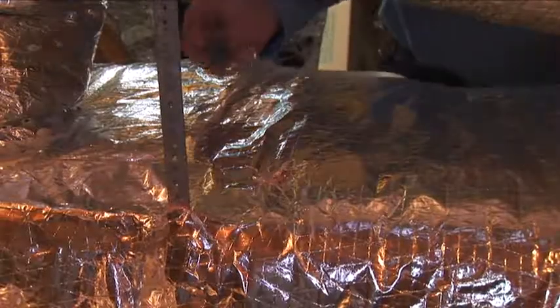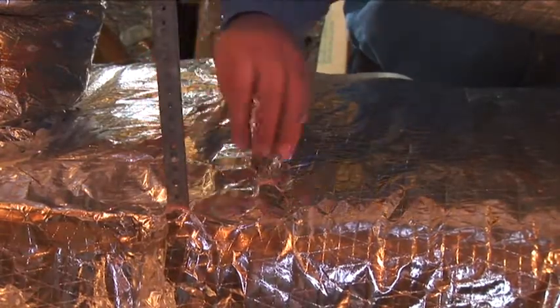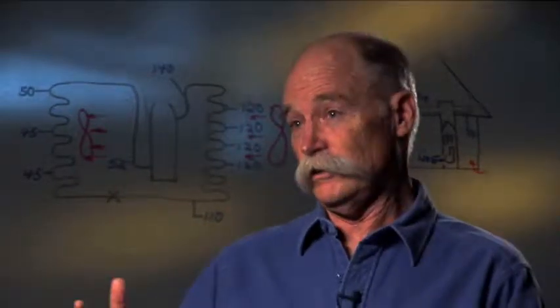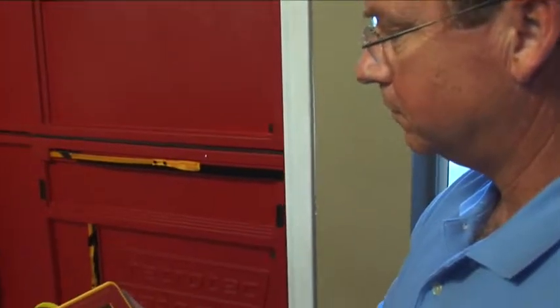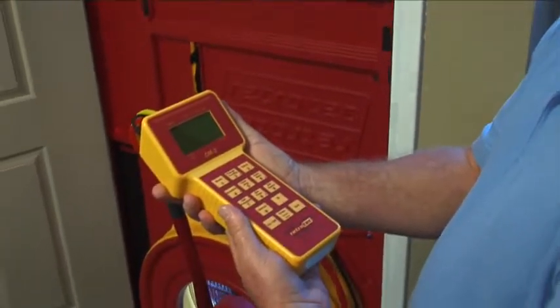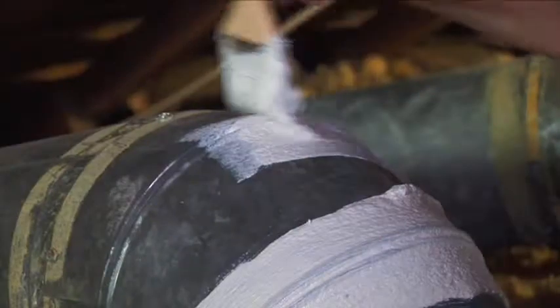It's very difficult to seal an existing duct system. Without proper measurements and diagnostics, you don't know if you've gotten to the leaks. There are contractors out there that'll say they'll do anything. But if they don't have the tools to test it, like duct testing, if they don't have the training to do it right, then you're not going to get what you're looking for. Basically, those people, when we go back and test their systems, they're still leaky.